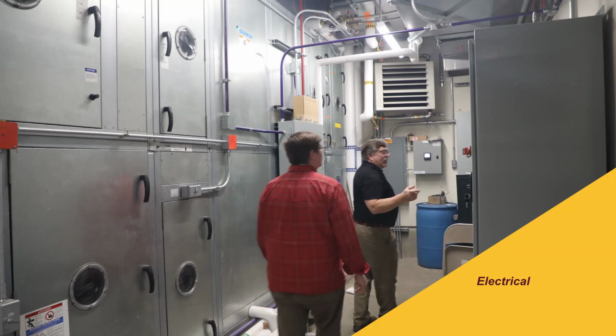As most of you know, the campus is interlocked with other buildings, and we have found during renovations that sometimes our buildings are supplied with utilities from other buildings. The idea is that every building must be a standalone facility. For example, the electrical service for all of the hall originally came from the transformers in another hall. By adding its own transformers, now it is not dependent upon any other building on campus.